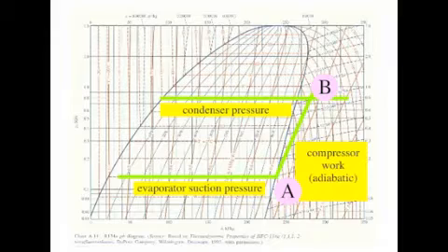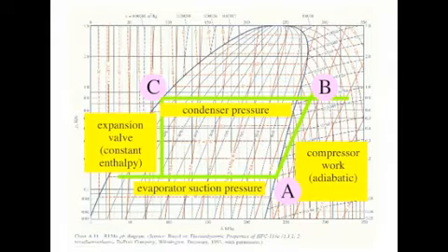As the refrigerant enters the condenser, the superheat is lost and the refrigerant gas begins to condense into liquid. As this occurs, heat is released to the environment. This process follows an isothermal line at this point until it reaches the saturation point for the liquid at point C. From there, the liquid enters the expansion valve, where the pressure drops to the low side needed in the evaporator. In this process, some of the liquid is converted to flash gas. At point D, the lower temperature liquid is ready to enter the evaporator, where it absorbs heat from the surroundings and is converted back to a gas.